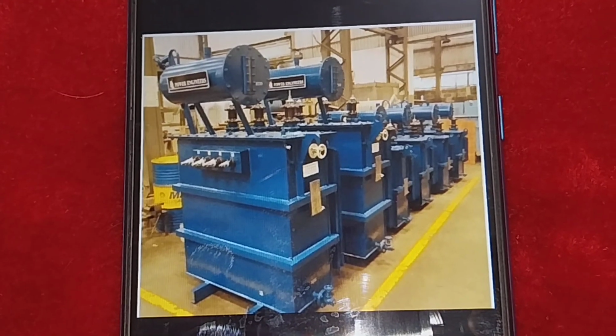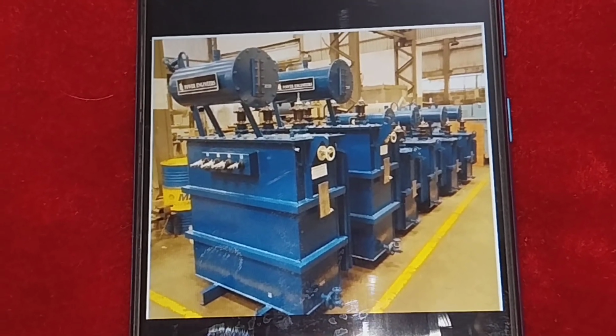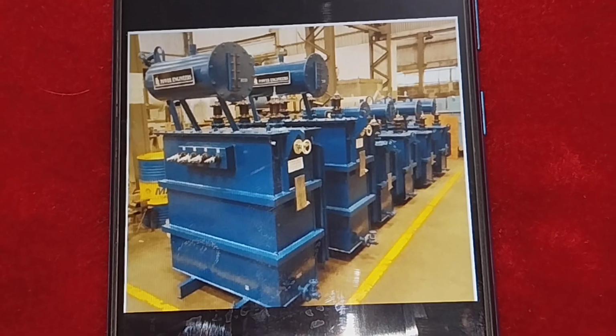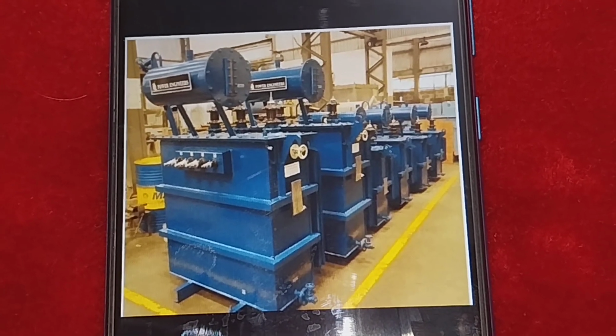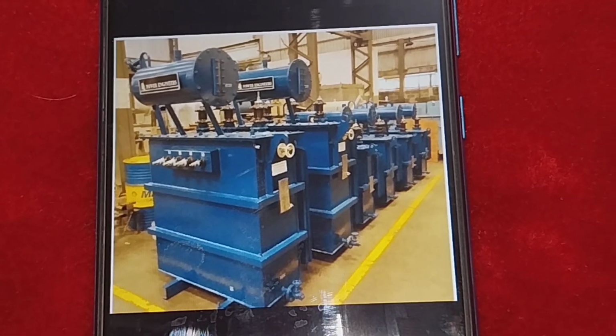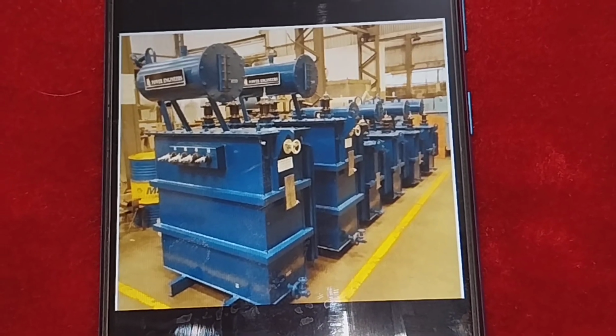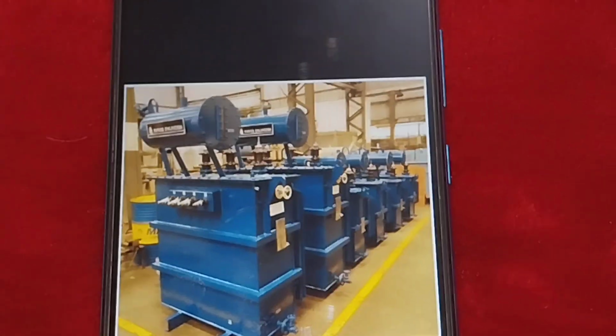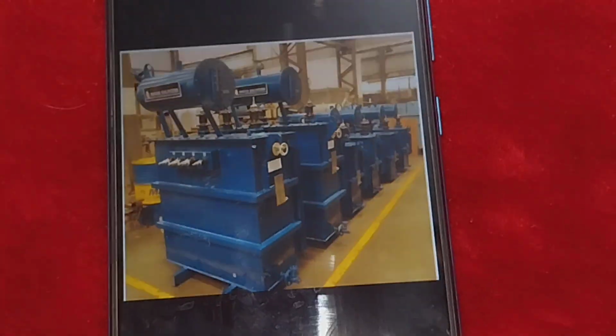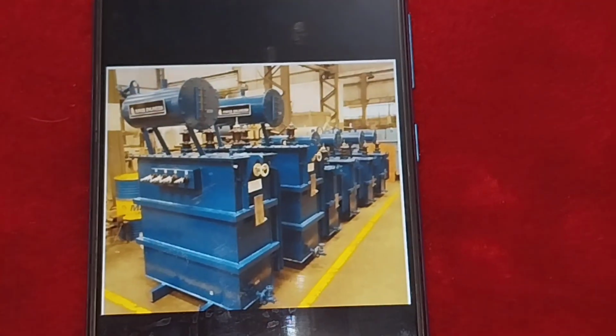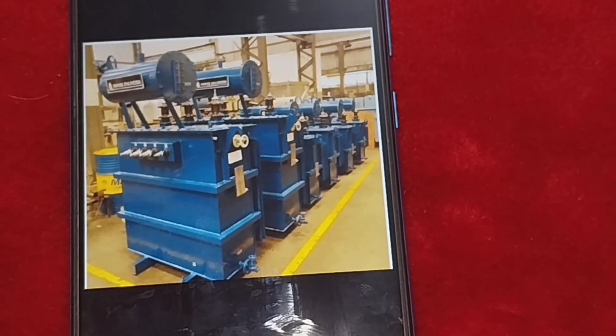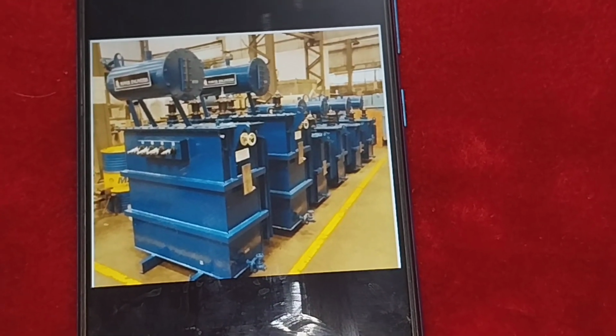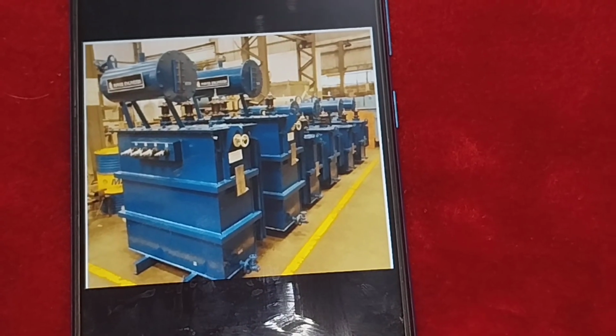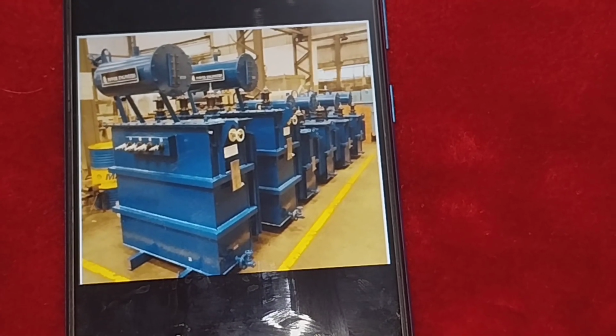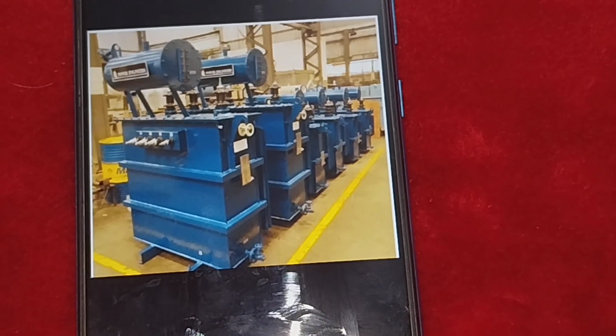Large numbers of transformers of a particular specification, when manufactured, are subjected to several tests as provided in Indian Standard 1180 and 2026. They can be categorized as type test, routine test, acceptance test, pre-dispatch inspection test, destructive test, and non-destructive test.